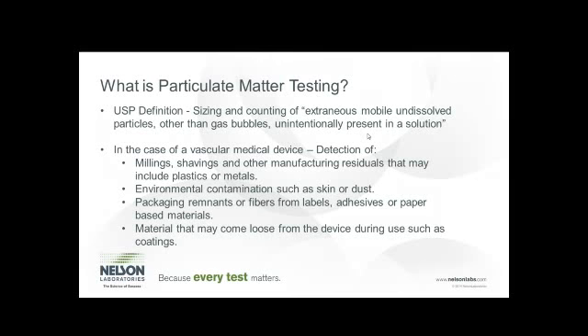In addition, there are a few other areas of particulate matter that may change this definition or add to it a little bit. In the case of a vascular medical device, we're also concerned about the detection of residual material from the manufacturing process, such as millings and shavings, which may include plastics or metals or other components not normally found in a solution. Also, environmental contamination — usually we find this as skin or dust, clothing fibers, things of that nature that just come from the environment that the device is being manufactured in. Also, packaging remnants are a concern. We often find fibers, adhesives, or paper-based materials that are present on the device from the packaging.